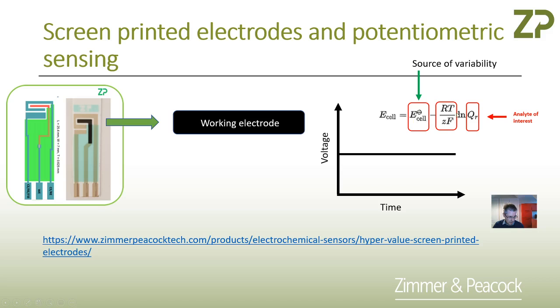That's not so apparent in the potentiometric sensor, because there's a constant — temperature, Faraday's constant — and no explicit physical parameters of the electrodes. But there is a subtlety: this offset here, the standard potential, is quite a sensitive parameter. So it's very hard to make a potentiometric sensor without doing at least a single-point calibration to understand this offset. This offset is not just a function of the screen printed electrode; it's also a function of the sample, making it quite a sensitive variable.